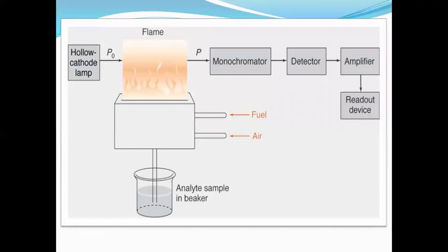This is the block diagram of atomic absorption spectroscopy. The first part is the hollow cathode lamp, which is the radiation source that passes radiation of different wavelengths. This is the flame into which our sample is introduced from the bottom, where the analyte sample from a beaker is passed through a fuel-air mixture and vaporized and atomized. A chopper is used in some instruments to convert steady light into pulsating light.